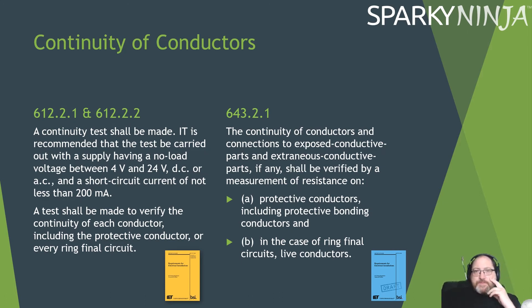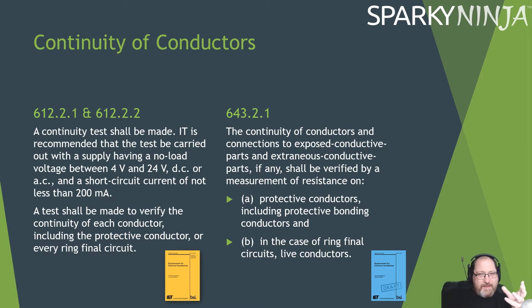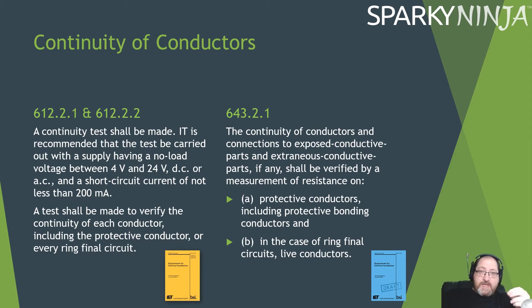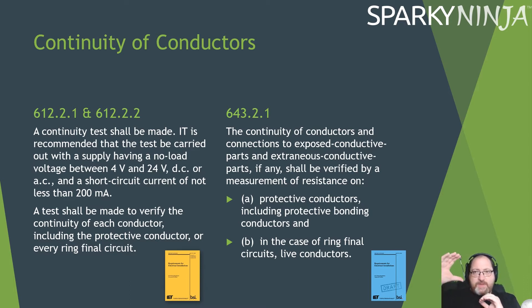Continuity of conductors — again, it's just a reword. The old regulation said it should be recommended to be carried out with a supply of no-load voltage of 4 volts to 24 volts — that's all gone. It now says the continuity of conductors and connections to exposed conductive parts and extraneous conductive parts shall be verified by measurement of resistance on protective conductors, including bonding conductors, and in the case of ring final circuits, live conductors. So that's the old two regulations, 61221 and 61222, compressed into one regulation, covering ring final circuits as well.